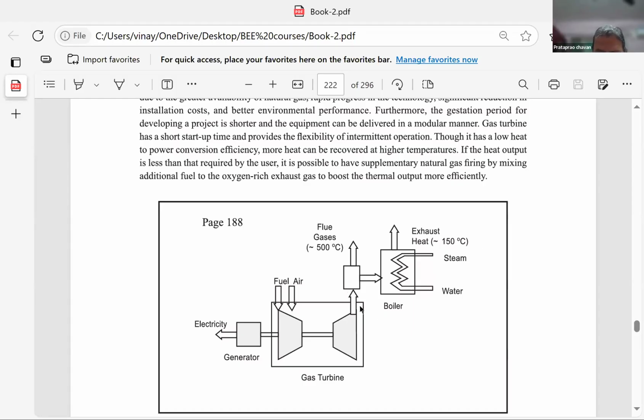Here, major loss is through the exhaust of the turbine, which is a very high temperature exhaust. So, if we allow this exhaust without recovering the heat from the flue gases, we are making a loss, and the turbine efficiency may be as low as 35%. But what we do, we recover this heat from the flue gases. Instead of allowing them to go out, we divert those high temperature gases and use them as a fuel in a boiler, which is an ordinary steam boiler, as we have seen.